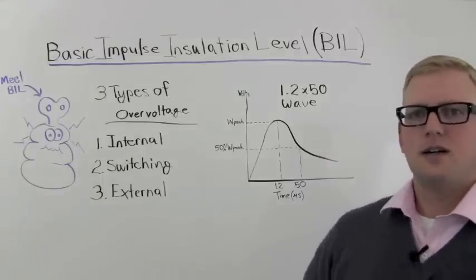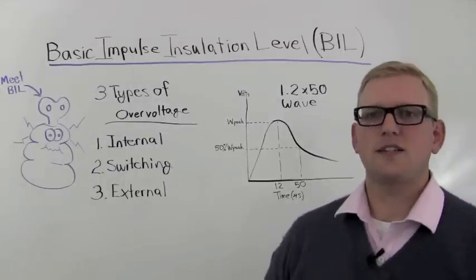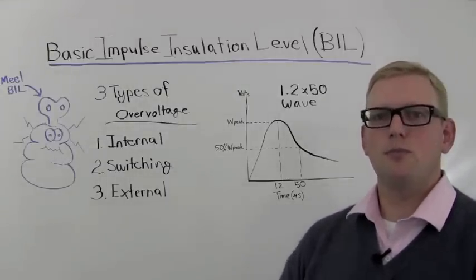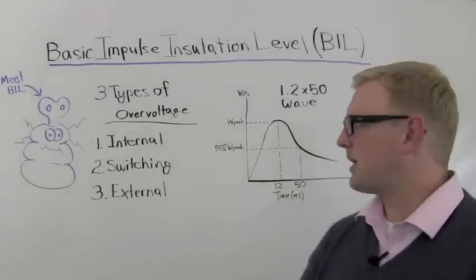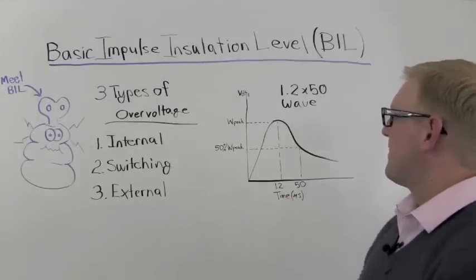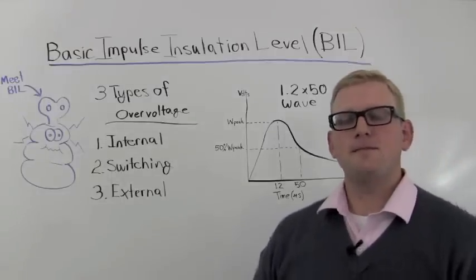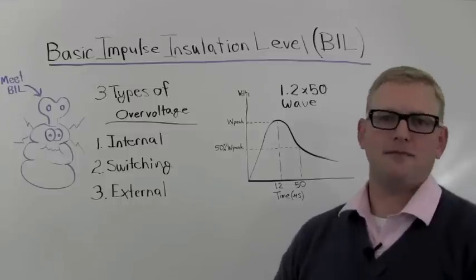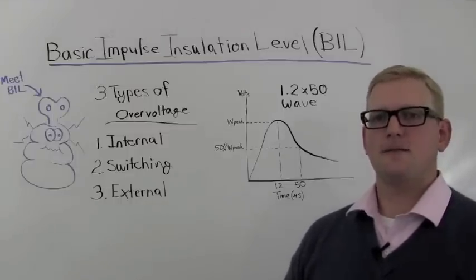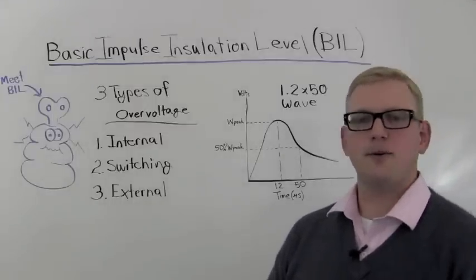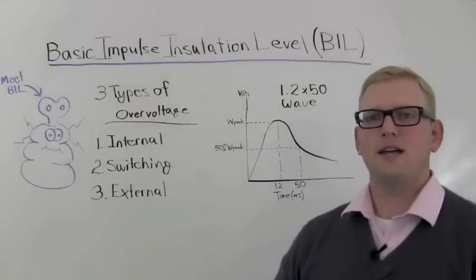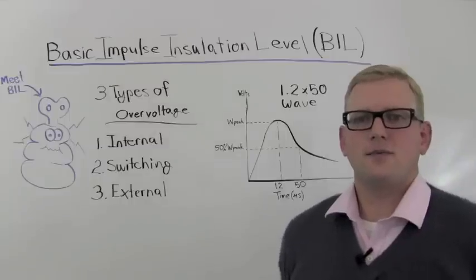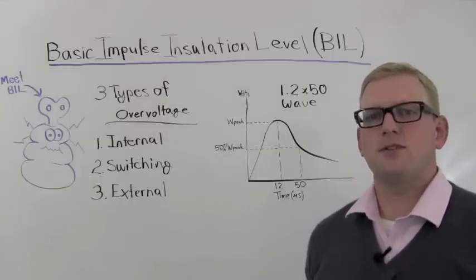So the 1.2 means: 1.2 microseconds past the event — say a lightning strike occurs — 1.2 microseconds later the wave peaks. And 50 microseconds after the event, after the lightning strike, the wave will be at about 50% of its peak. This is the standard waveform used to classify BIL and to allow engineers to select a piece of equipment that can withstand a certain level of voltage surge.